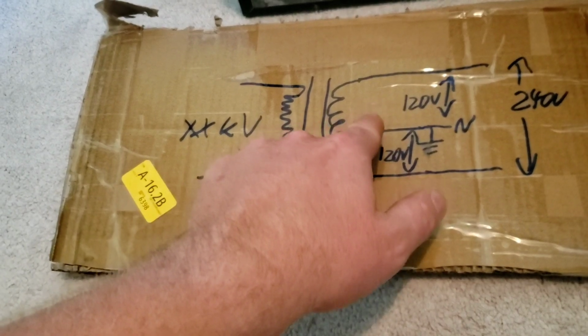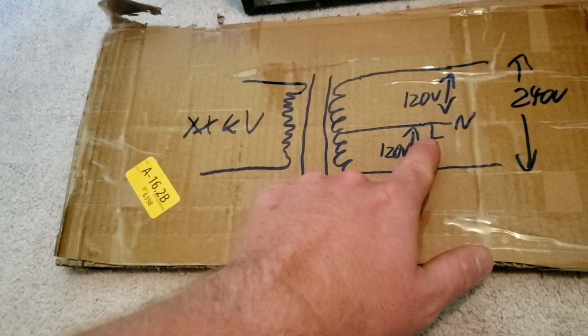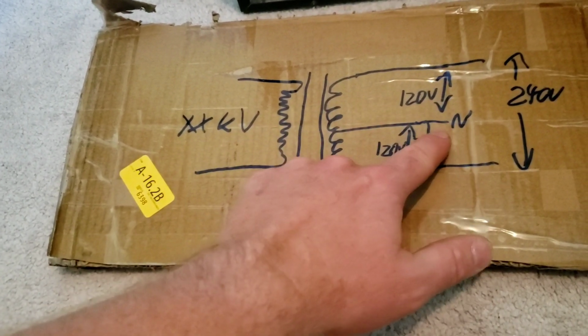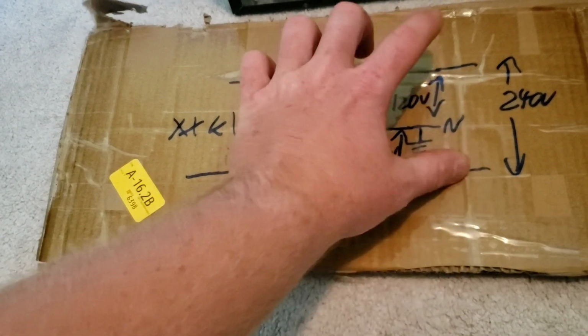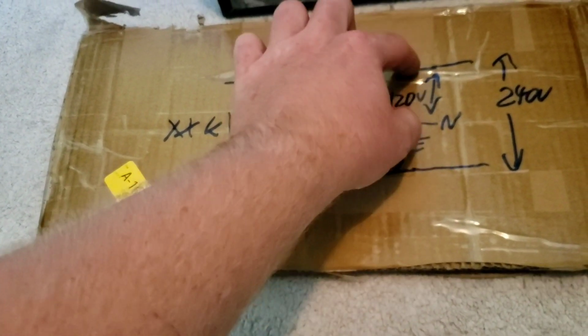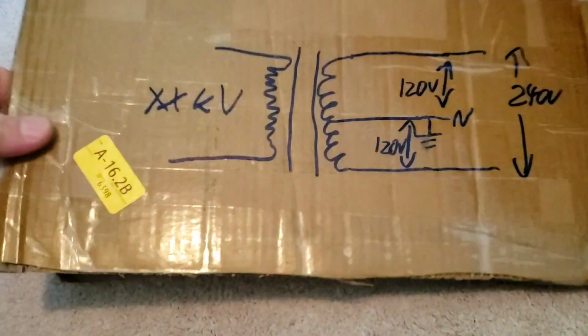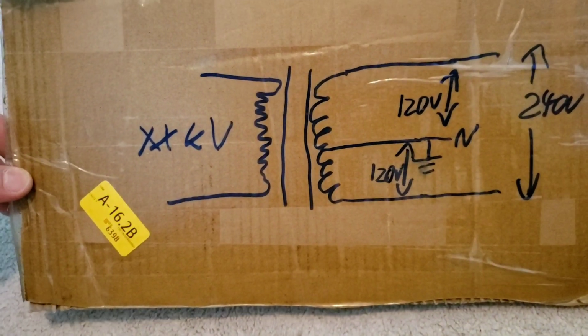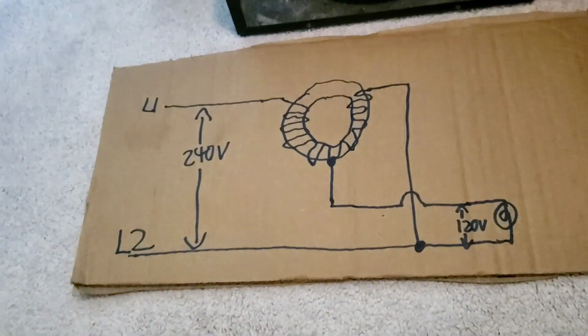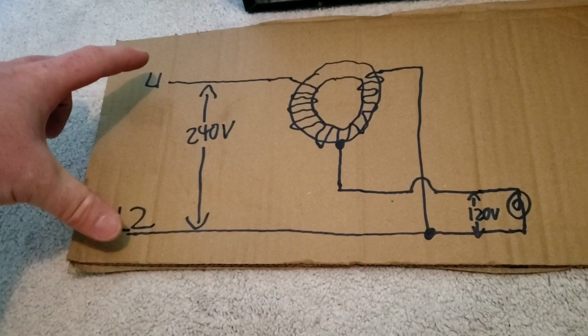It also has the benefit of having - you can bond the center part, where you have a neutral, you bond it to ground, and you have hot to hot - these are two hot conductors. This is hot to neutral, this is hot to neutral. So 120, 120, 240. Once again, pardon my terrible drawing, but this is kind of how it looks, and that's why I can accomplish getting 240 volts.